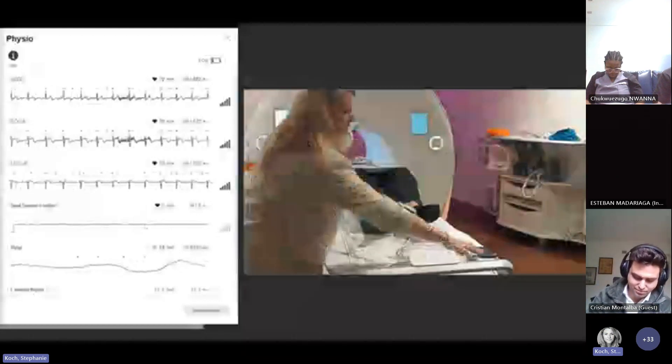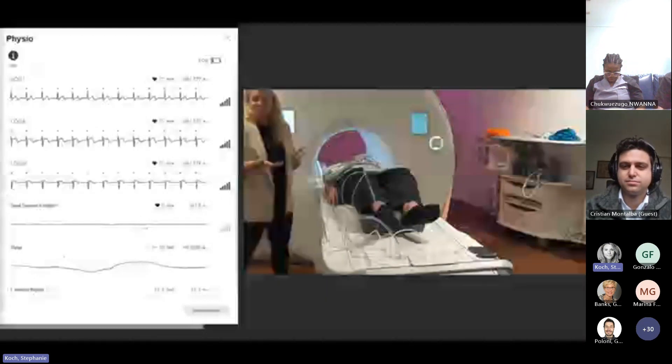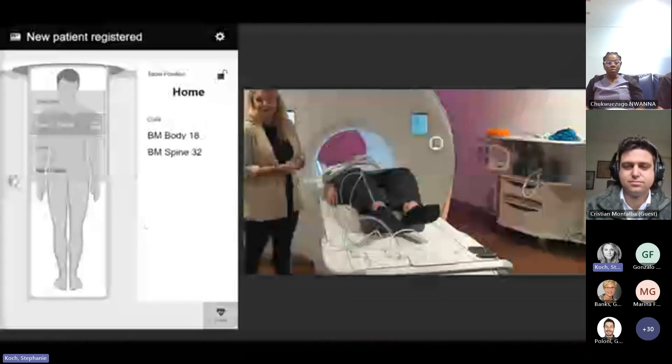Then we give them the alarm roll as well. Everything is okay? Perfect, good. My patient is now directly ready to go into the bore, and you can see when I press the card towards the reader, I only need to press it and that's it. I can easily bring my patient directly inside. I only need to take care of my switch and the microphone.